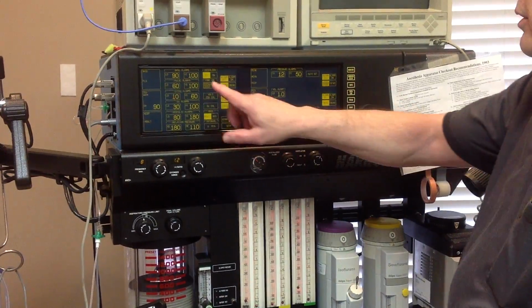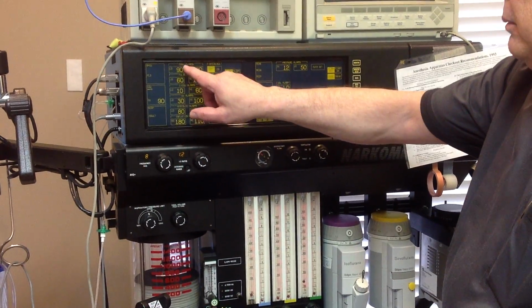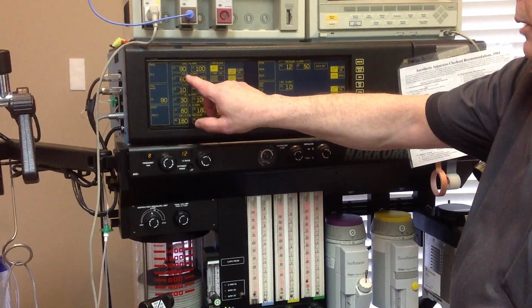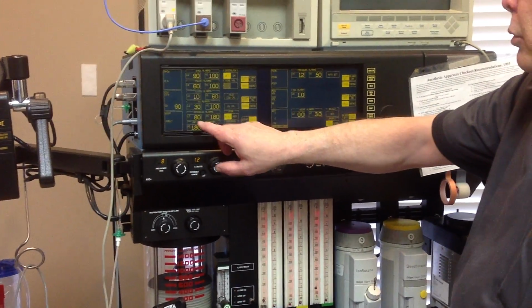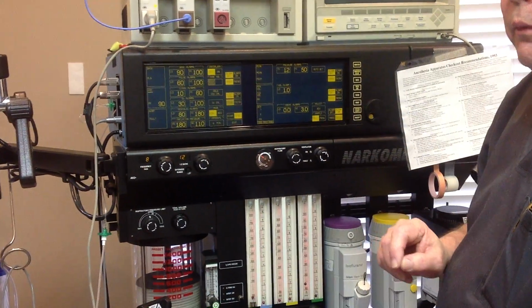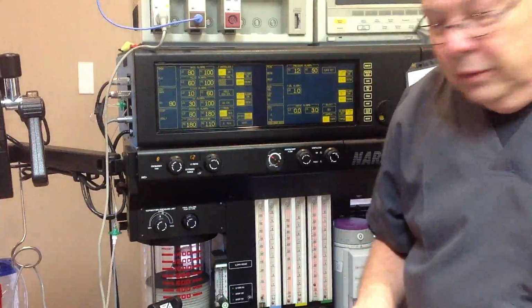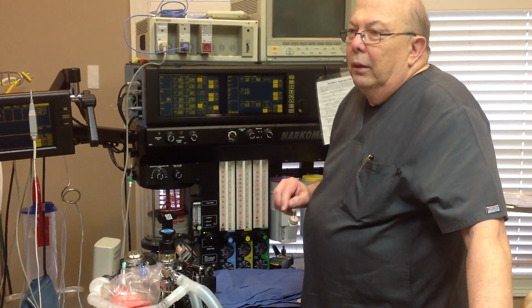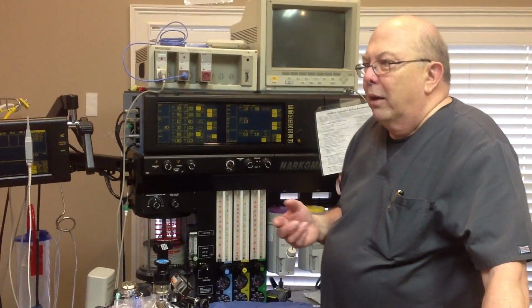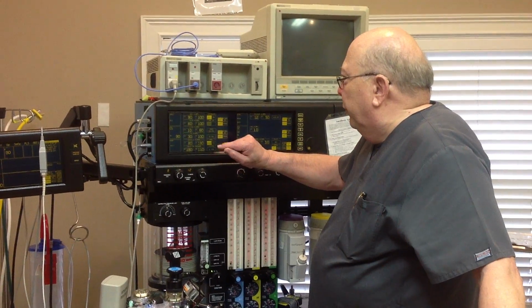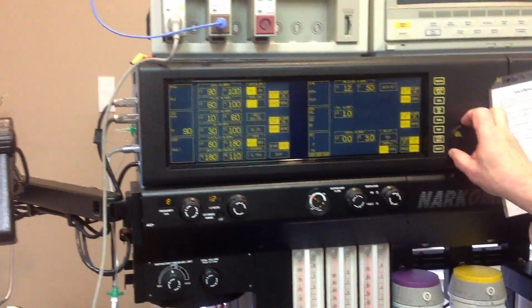is my monitor setup window, so that would be all here. So this is all my alarms for my SaO2, my pulse, my CO2, my FiO2, and then my blood pressure settings there. And then over here, interlock is if I had a blood pressure cuff on this arm and my pulse oximeter on the same arm. So if the blood pressure cuff goes up, there's going to be an alarm. So I put it on interlock, and it will not alarm. So it's not driving you crazy. Okay. And then I hold CO2 cal. Here's my pulse oximeter sound. Here's my other sound you've got to get used to. Okay.